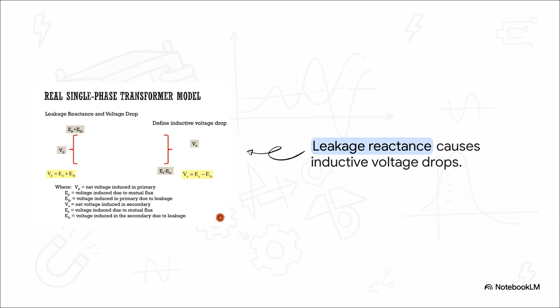And this perfectly illustrates the real consequence of that leakage. This stray leakage creates what we call leakage inductance, which in turn has a leakage reactance. Now you might be wondering, why does this matter to us when we're studying the grid? Because ultimately it causes unwanted inductive voltage drops across the coils. The net voltage you're actually getting out of the transformer gets dragged down by this leakage, which directly eats into the overall efficiency of your power transfer.